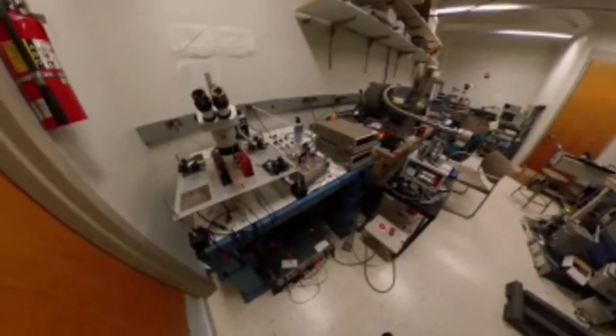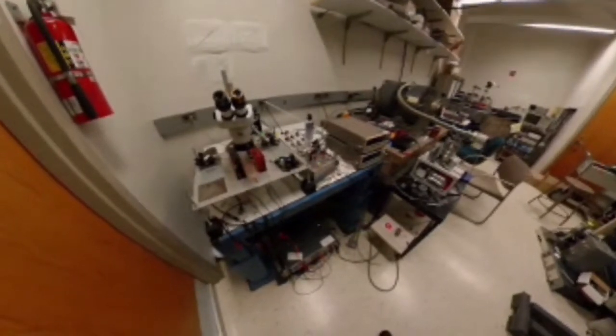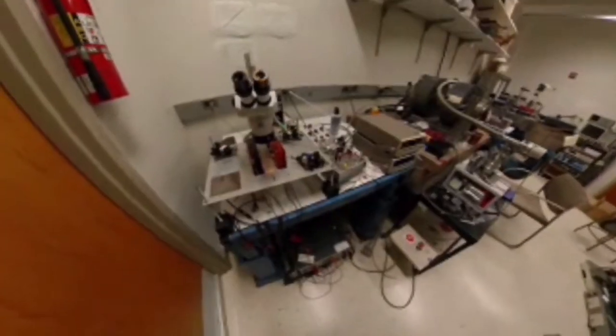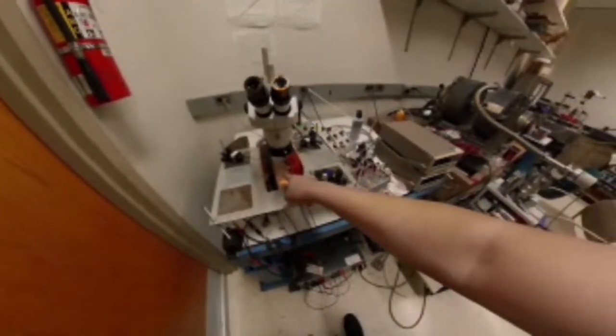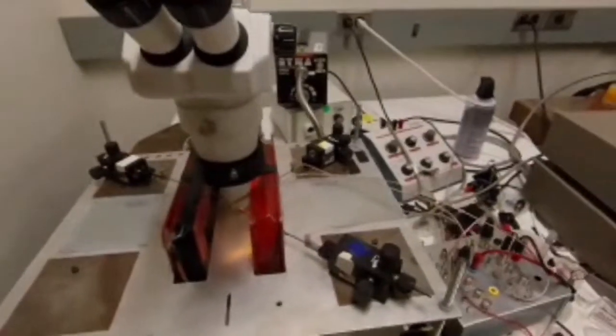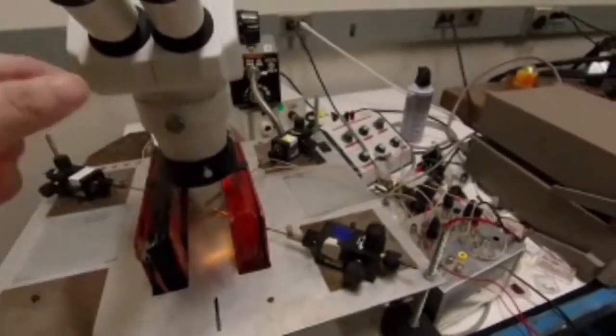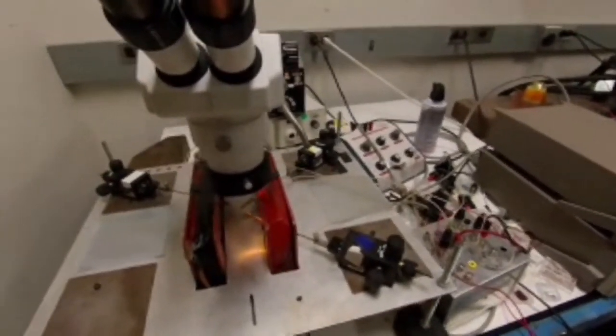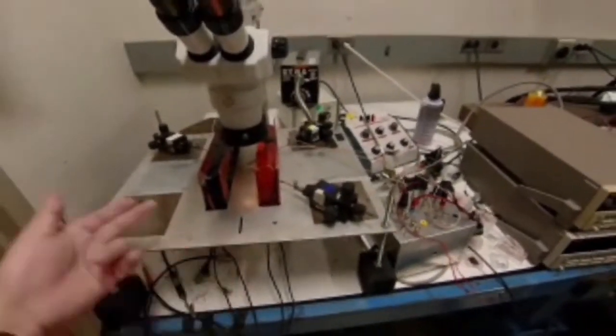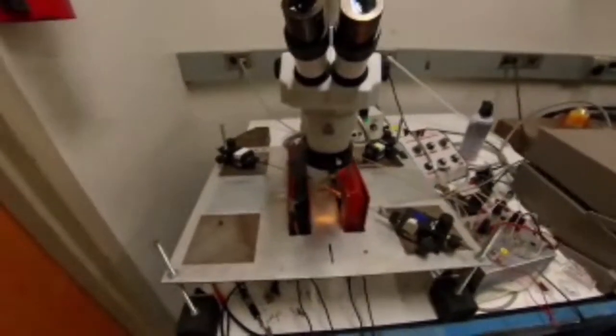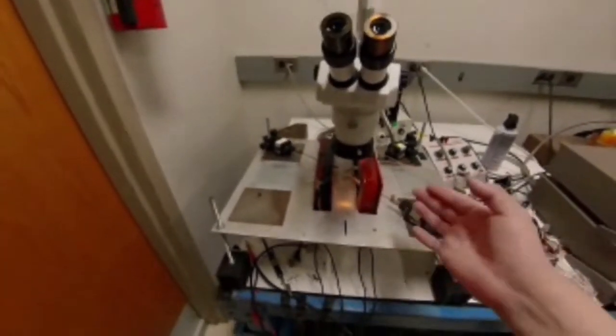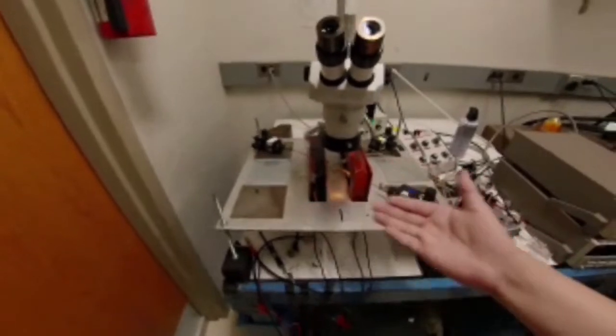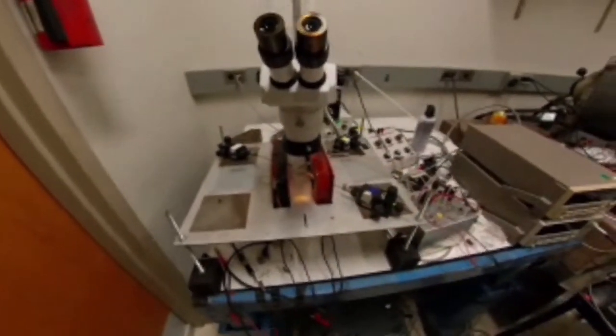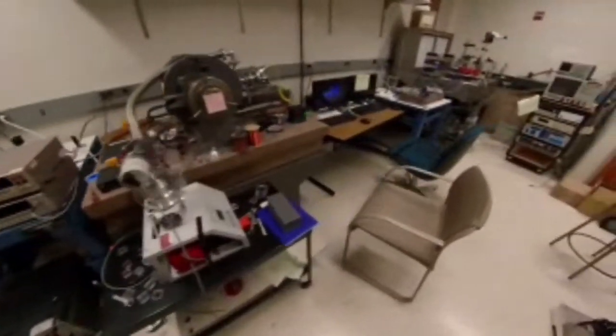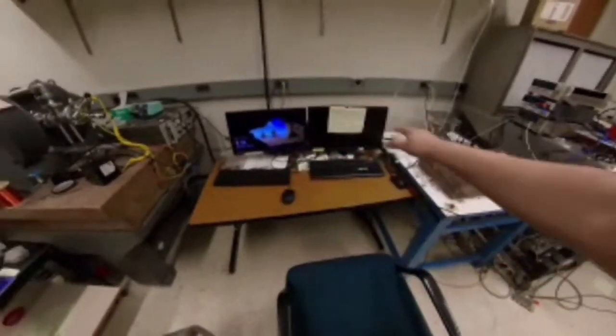So this laboratory is dedicated to testing materials, or mostly testing devices. You can apply these metal probes. There are tiny needle probes here on this testing stage, and it allows you to apply a specific voltage or current to a device, and then you can also control and apply the magnetic field using these electromagnetic coils. The magnetic coil can be placed in this configuration, horizontally or vertically. And then the setup can be programmed using this computer here.